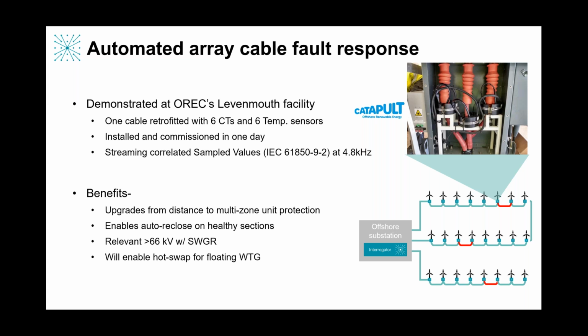Now, that's particularly useful if you're economically, if that's a scheme that's using cables bigger than 66 kV, which is going to be the norm in the future, and where operators are now considering putting switchgear in the turbines, because especially for floating wind, that means you're going to be able to do delayed auto reclose, and you can hot swap floating turbines in and out of a circular array without disturbing the protection scheme and causing a false trip and a total outage. So it's going to be a critical enabler as wind farms get bigger and cables get longer and carry more economic value.